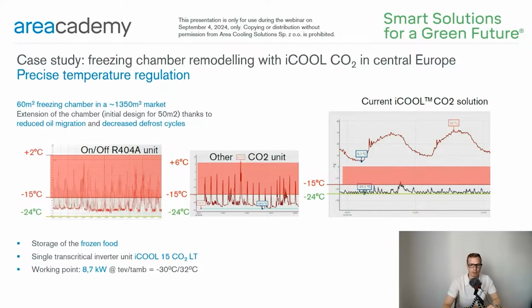And because of this, the solution was changed to the CO2 on-off technology, the graph in the middle, which also was not provided by Area Cooling Solutions. The situation was the same and sometimes even worse because the temperature reached even plus 6 degrees Celsius.